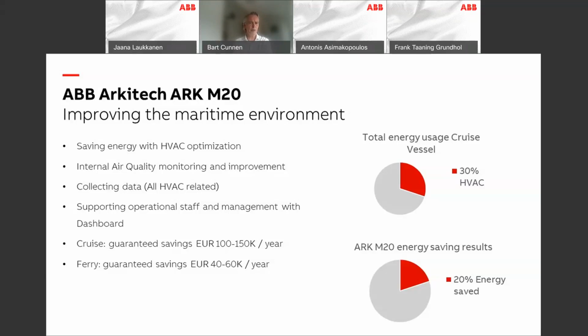We're saving a lot of energy. On a cruise vessel, it's at least 100 to 150K per year, and we guarantee that. On ferries, it's about 40 to 60K per year. I'm not going to tell the percentage of HVAC consumption on a vessel, but what I can say is that from the total HVAC consumption, our system can save up to 20%.